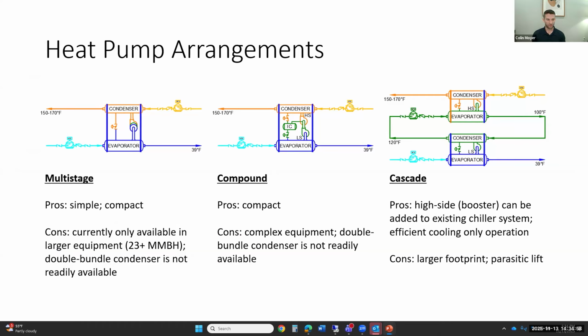We've got at the left depicted a multi-stage electric driven water-to-water heat pump. In the middle, a compound unit, and on the right, a cascade system. So the multi-stage unit is one of the latest emerging technologies on the market, and it was recently released in the equipment that's about 23 to 27 million BTUs per hour heating capacity. It uses a 3-stage compressor. So that's a single semi-hermetic electrically driven compressor, but it has 3 impellers in it. And because it's doing a lot of lift from 39, 40 degree chilled water, all the way up to its capability of 170 degree hot water.